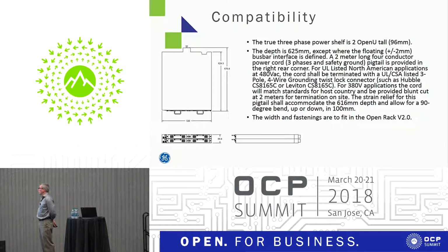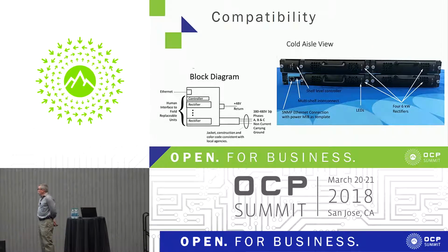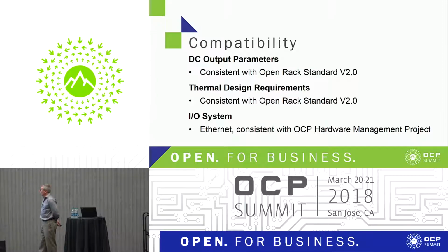Compatibility, it's obviously designed around the Open Compute physical dimensions. It fits in the short 48 volt rack with the associated UL listings and dimensional compatibilities. It's designed currently to fit with the width and the fastenings of the Open Rack 2.0. In terms of compatibility, looking in from the front, we've got the two diagrams that we saw before. Obviously, it's compatible with the 48 volt requirements of the system, as well as the 480 volts AC input. The DC output parameters are consistent with Open Rack Standard V2, as are thermal design requirements.